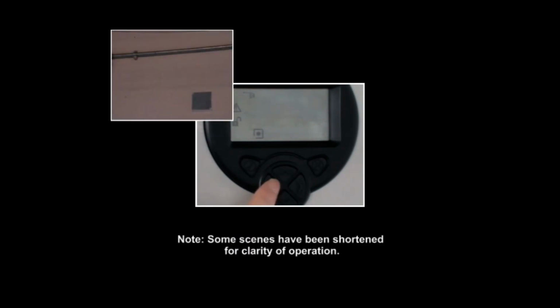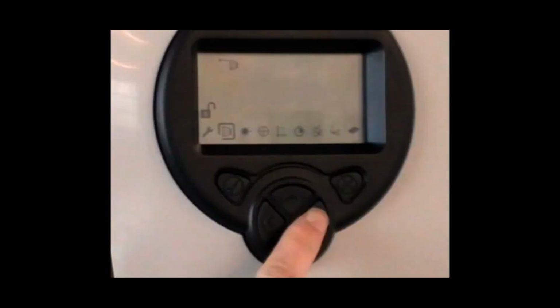Now turn on the laser by selecting the laser icon on the engineering menu. The system will be in fault during laser alignment. Use the arrow keys on the system controller to steer the laser until it falls on the reflector. Once this is done, select either the tick or cross button to turn off the laser. You are now ready to perform automatic alignment of the chosen detector.